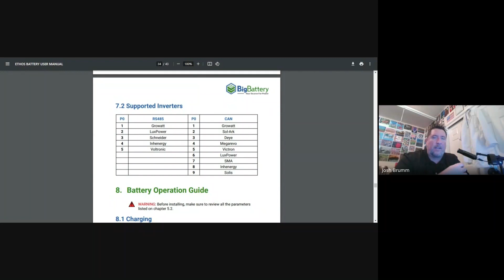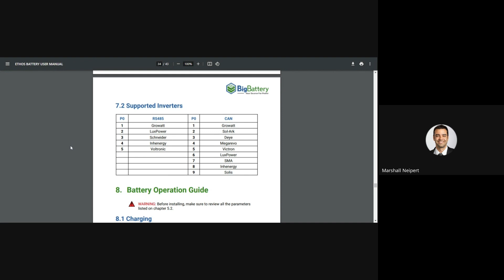That's correct. So if you don't have communications or CAN bus, what we'll usually do is set the parameters correctly. That's really easy - you're just going to set the high voltage parameter, the low voltage, and then your float, and it's done. You would set it by voltage, and on the battery there's nothing to set. The battery will function normally standalone with no comms. If it's wired up and the breakers are turned on, it'll act like just a 48 volt system.